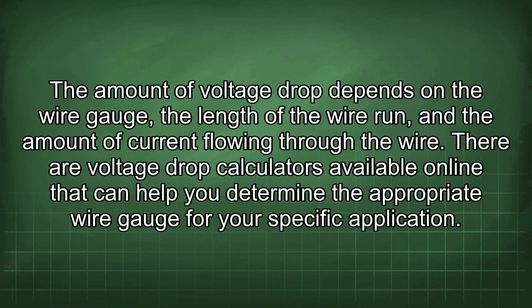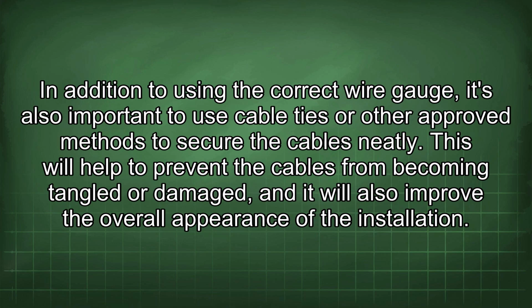The amount of voltage drop depends on the wire gauge, the length of the wire run, and the amount of current flowing through the wire. There are voltage drop calculators available online that can help you determine the appropriate wire gauge for your specific application. In addition to using the correct wire gauge, it's also important to use cable ties or other approved methods to secure the cables neatly. This will help to prevent the cables from becoming tangled or damaged, and it will also improve the overall appearance of the installation.